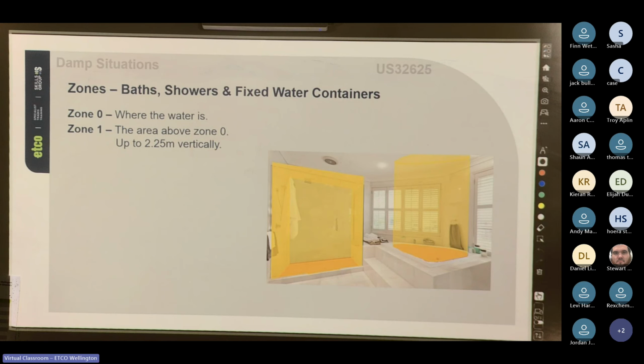So, for example, if I'm standing at the ground and there's a wire above 2.25 meters, it is considered safely out of reach of me unless I was to grab a ladder. So that's another part of 3000, but basically if there's a platform permanently affixed in an area, we take it from the height of that and up. So if we've got a bath and it's, yeah, I know if you're tall, but it's what we define in 3000 as safe out of touch. Again, it's the number that they decided upon. Probably they took average height people at the time they wrote it, and that's what they went with.